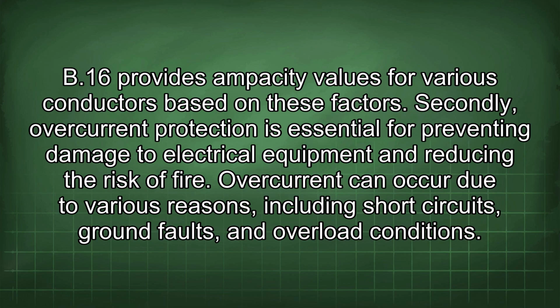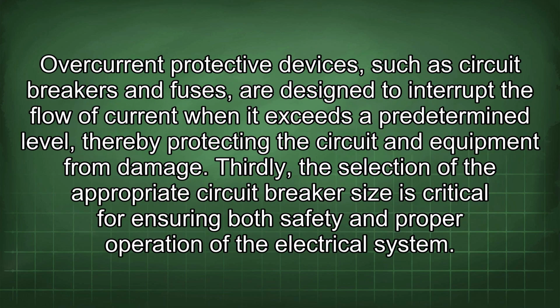Secondly, overcurrent protection is essential for preventing damage to electrical equipment and reducing the risk of fire. Overcurrent can occur due to various reasons, including short circuits, ground faults, and overload conditions. Overcurrent protective devices, such as circuit breakers and fuses, are designed to interrupt the flow of current when it exceeds a predetermined level, thereby protecting the circuit and equipment from damage.